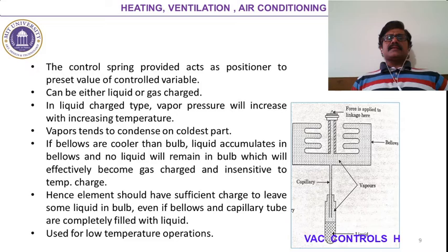Now this is undesirable. It is essential that this element should have a sufficient charge to leave some liquid in the bulb all the time, even if the bellows and capillary are completely filled with liquid. So both the bellow as well as the bulb can be filled with liquid, but the bulb should retain some for the normal operation of this particular bellow. Such a bellow is used for low temperature applications.